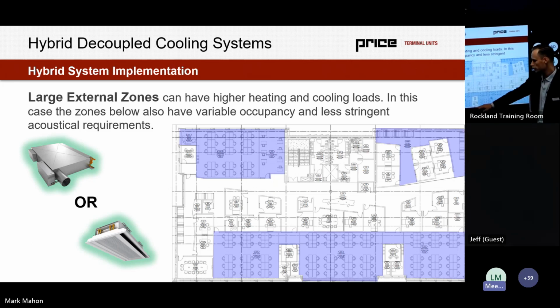So this is actually facade on the south side and on the north side. So these are both external zones that we can see on screen here. And these are larger zones with higher heating and cooling loads. In this case, they also were very variable occupied. So these are open office environments. We can see we have these groupings of 6 or 4 tables or desks spread out throughout the square footage here. And generally these spaces, because they were so large and so open, could have higher airflows and still manage lower acoustics. So can anyone tell me in the room, if you were going to suggest a chilled beam or the fan-powered terminal in this case, which way would you lean?